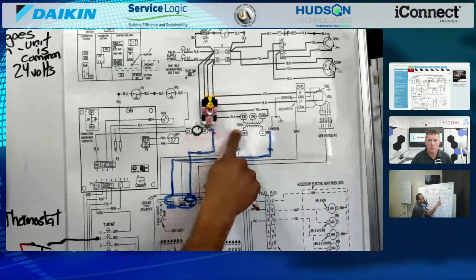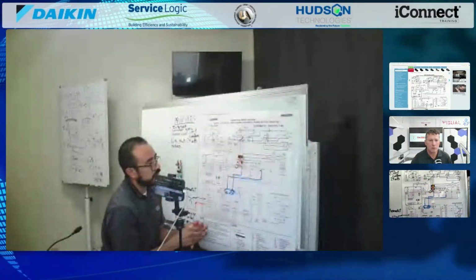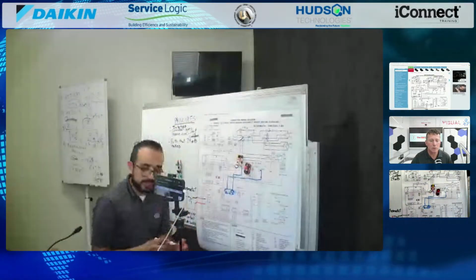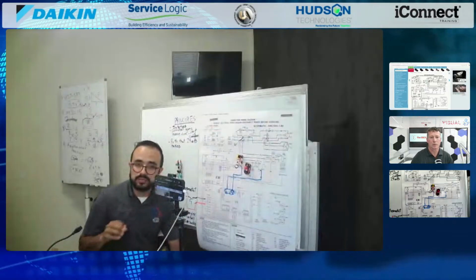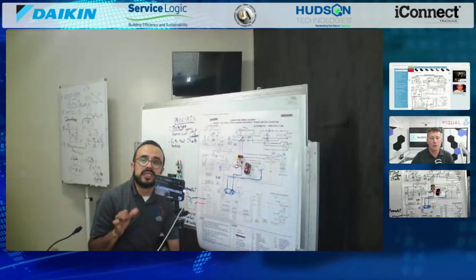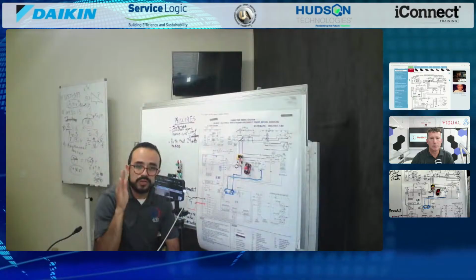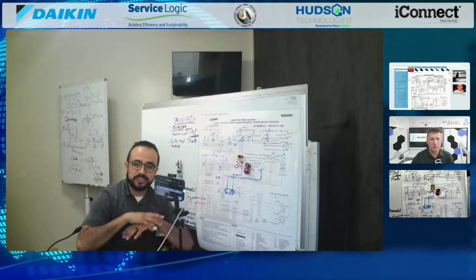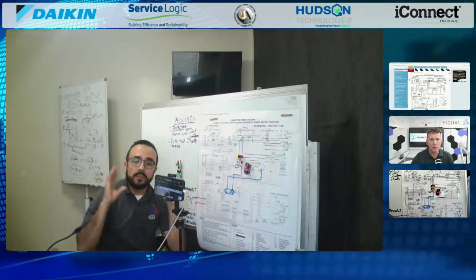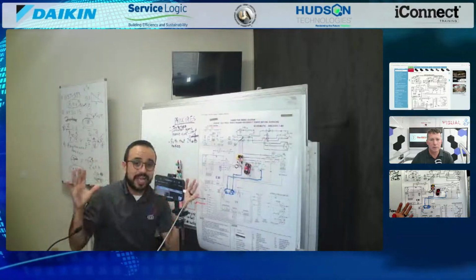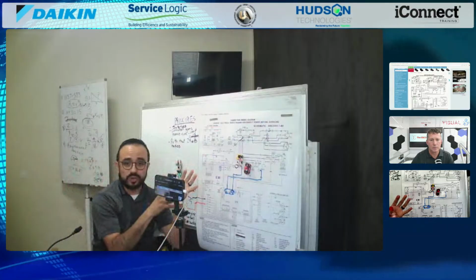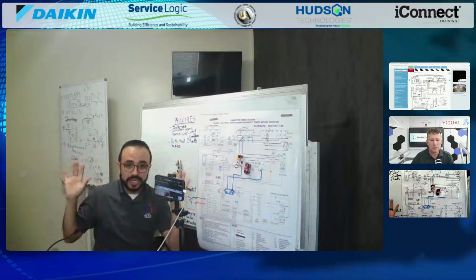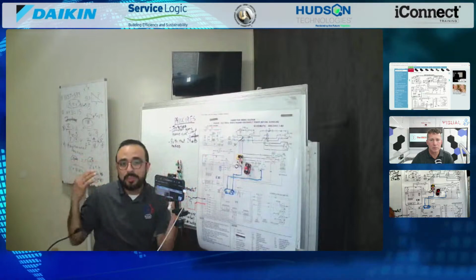We need to understand the path that Mario, the 24 volts, needs to take. This is where a lot of students have a hard time understanding the path that 24 volts takes. It doesn't matter, as long as it's conventional - Mario, or 24 volts, takes a path to make it to the contactor coil. That's a given, it's going to happen. We just have to find out the path it takes.